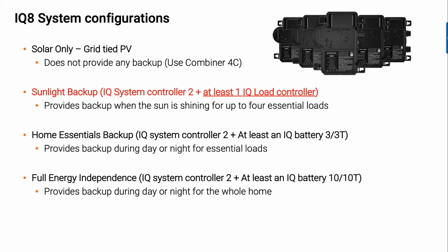Now, there are requirements for this. For most of you, if you've taken the sunlight backup course, you know you need an IQ System Controller 2 and at least an IQ Load Controller. Remember, this is the load controller I mentioned earlier. These are two mandatory components to install a sunlight backup system. And this is a backup system without batteries. There are no batteries. It's just using the sun to create power for a home if the utility fails. All right, so that's sunlight backup.